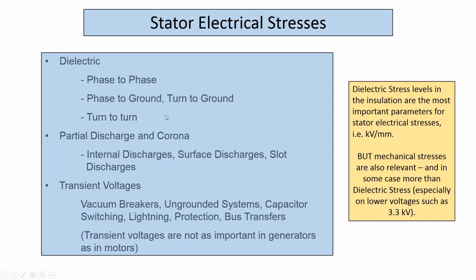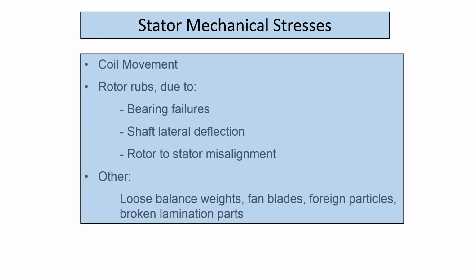And in any medium voltage machine, you are going to have these stresses, you are going to have the failure mechanisms, so it's important to consider them. And in the proposal that I make, I believe that dielectric stresses are still very important because they involve 6.6 kV machines. But you'll also see that mechanical stresses are often the key parameter to consider. So stator mechanical stresses, you get typical stator mechanical stresses. They exist on all machines, whether they're 3.3, 6.6 or 11 kV. But the mechanical stress that I'm concentrating on, as I've said, is the thermal cycling stress.